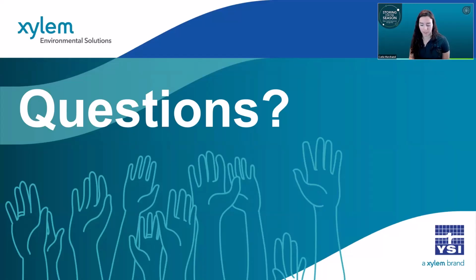It depends what kind of instrument you have, but with EXO and ProDSS instruments, you would just be swapping out this top cap here, this module that has the reference solution and bulb in it. The sensor body is going to last you for a long time. And then there are other instruments that YSI has where they're smaller sensors. I don't have any here on me, but you would swap out the whole sensor instead. So, when to know to replace them.